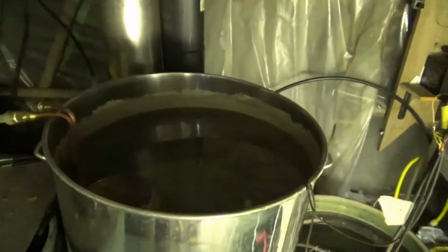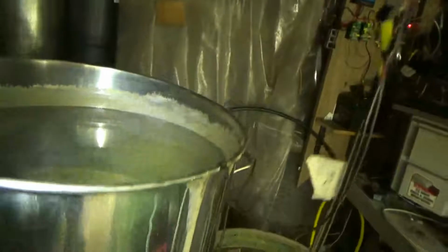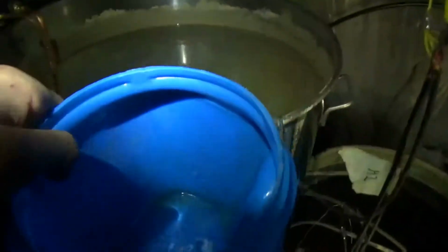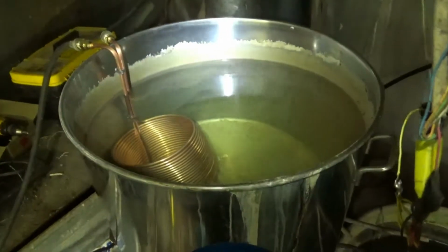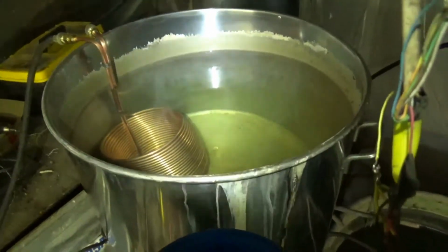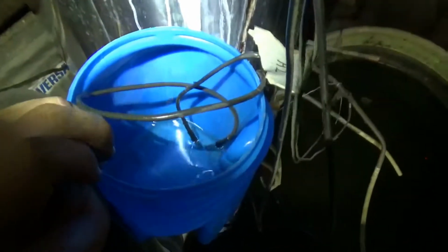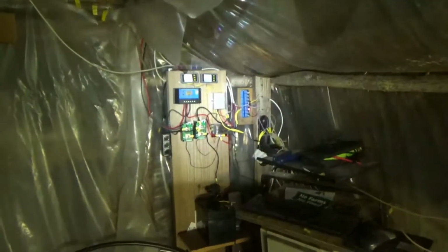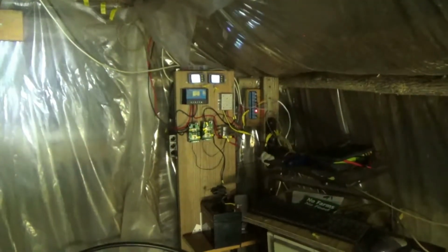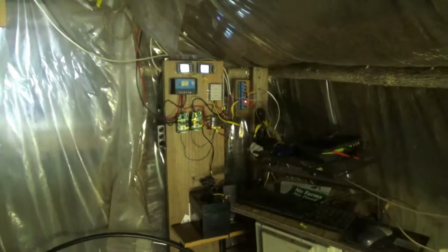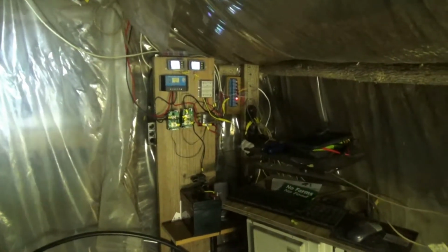So what we'll do is take a cold water source and try this on my knee while I hold the camera. I've taken the two temperature sensors out of there and put them in the cold water. In the next minute or so, you'll see the relay trip off. This system checks temperatures every single minute.